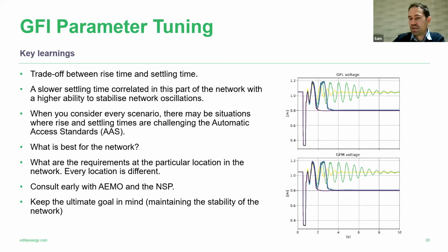These lines represent a range of different settings we could use with the grid forming inverters. In some situations the grid following inverters actually trip, while in other scenarios there are varying degrees to how quickly the oscillations are damped. This was an important aspect of the studies: figuring out what problem we're actually trying to solve.